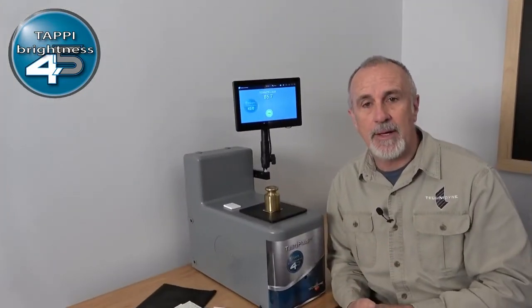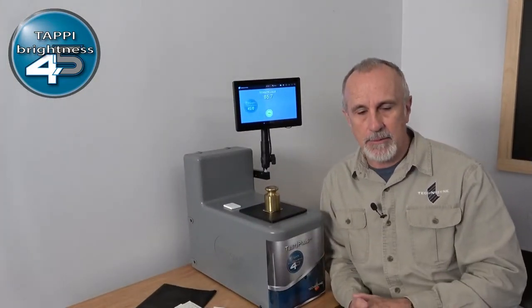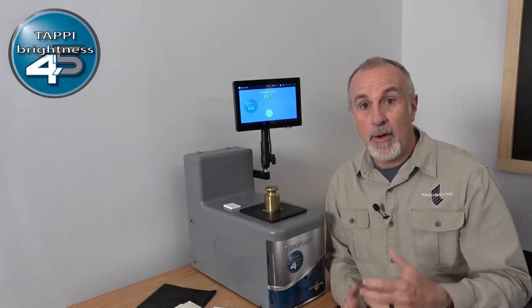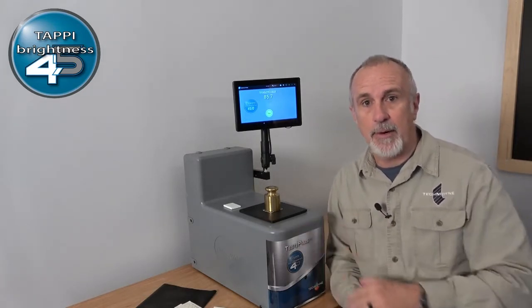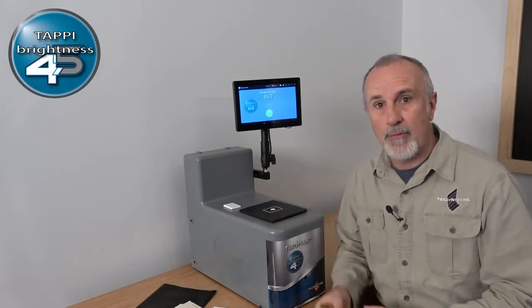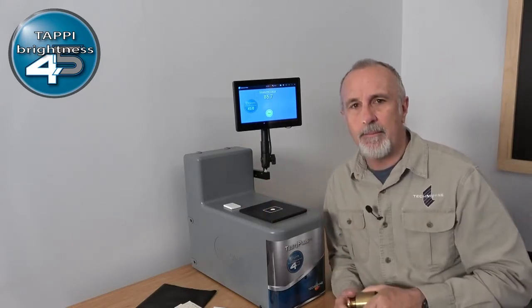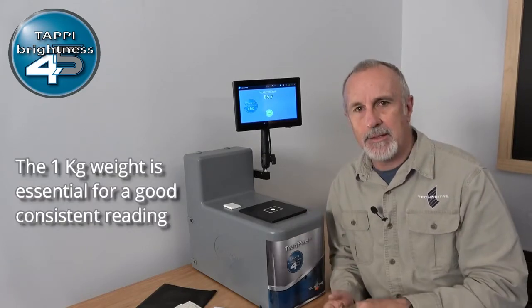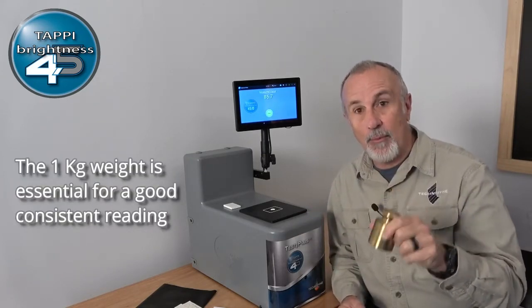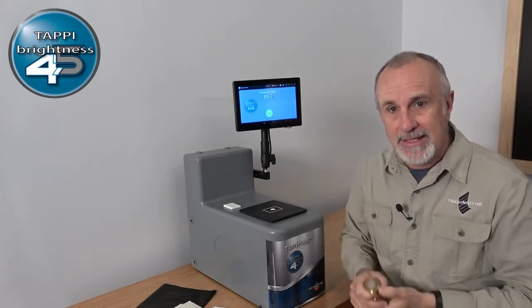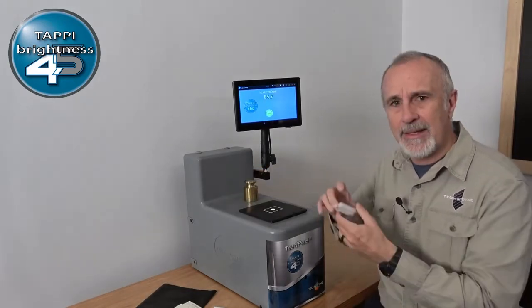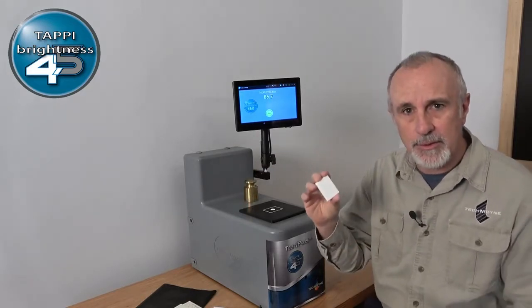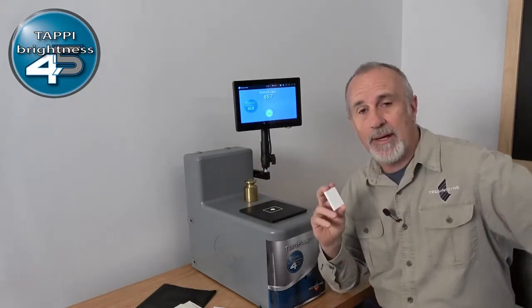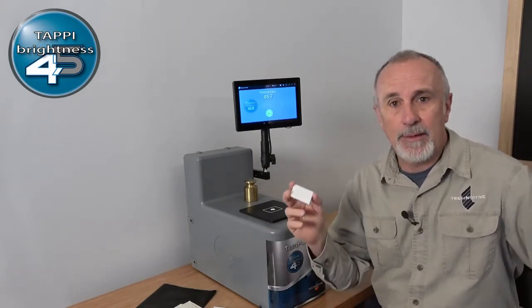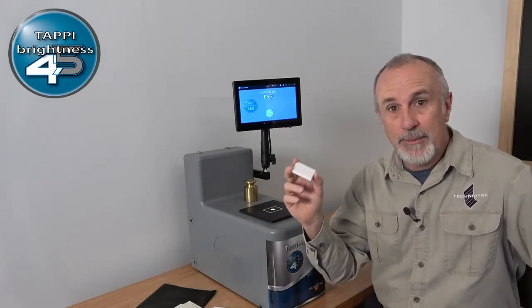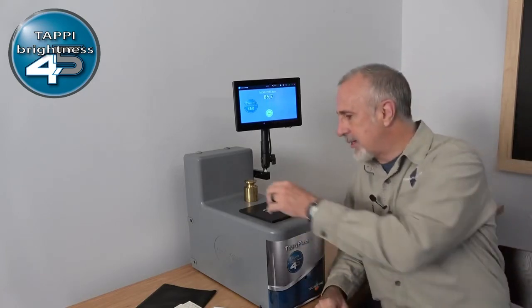Now we're back and we're ready to begin the calibration sequence on the instrument. Before we get started with that, let's talk through the things that you will need to make sure you can get a good calibration with the instrument. One, you always need to make sure you have the 1 kilogram weight. When you're measuring on a directional instrument like this, the TAPPI method calls for a 1 kilogram weight to be the backing, so you have a consistent backing. You will need the opal tile that came with the instrument. This is your working standard. You're probably using this already on a daily basis, maybe a shift-wise basis, to keep the instrument in calibration. So we'll go through that step as well.